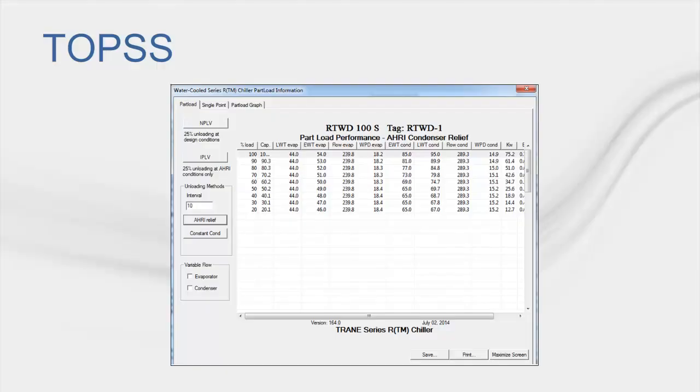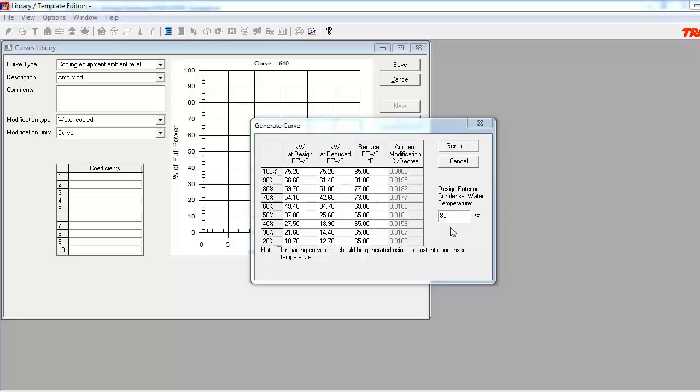If we go back to the TOPSS program and the View Graphs and Charts area, we can see that if we leave the Interval input as 10 and click on the AHRI Relief button, the program will provide us with the data that we are looking for. You can see the Percent Load column, the Entering Water Temperature Condenser column with Reduced Temperatures, and the Modified KW values. Back in the curves library, you can see that I have populated the required data provided by TOPSS into each of the columns. Note that the Ambient Modification Percent Degree column is populated with a calculated slope curve coefficient for each load interval.